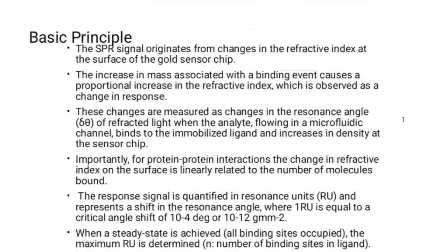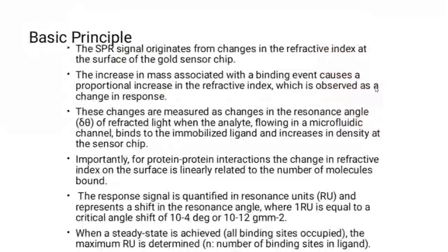The basic principle is that the SPR signal originates from changes in the refractive index at the surface of the gold sensor chip. The increase in mass associated with a binding event causes a proportional increase in the refractive index, observed as a response unit change. These changes are measured as change in resonance angle. The change in refractive index on the surface is linearly related to the number of molecules binding — so we can calculate stoichiometry from SPR as well. To summarize: first is kinetics, second is affinity, and third is stoichiometry.